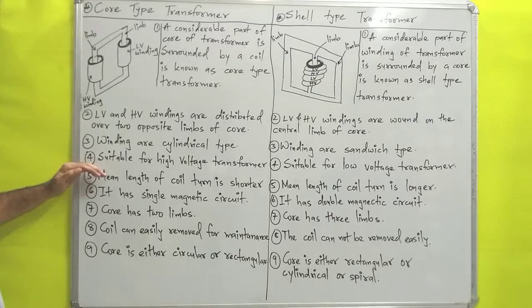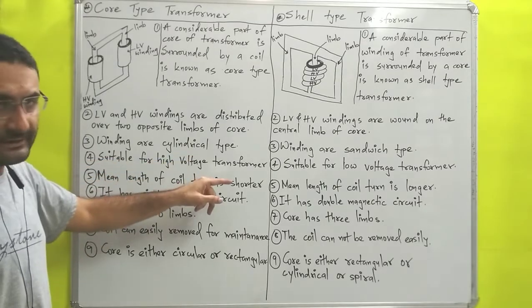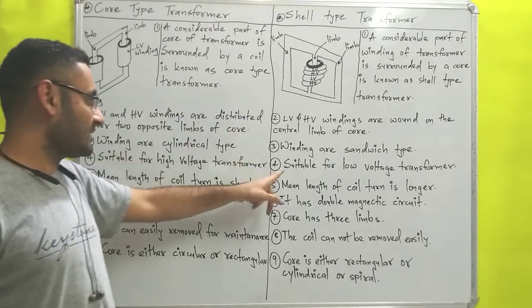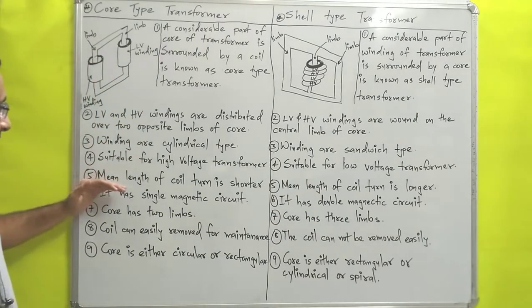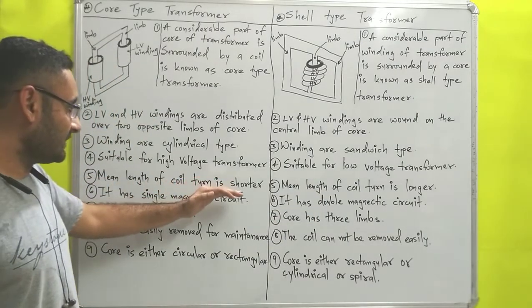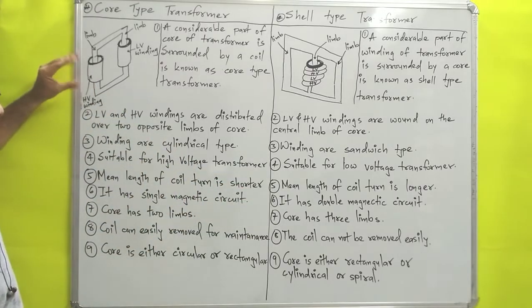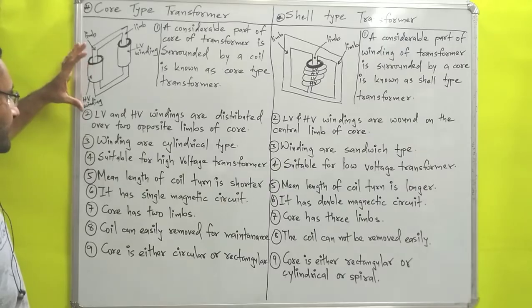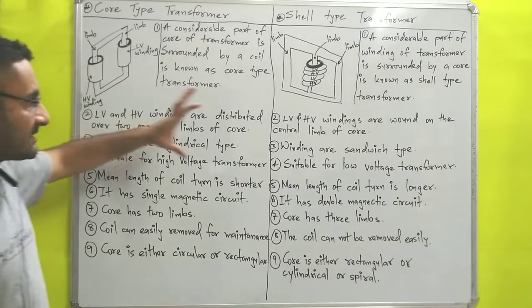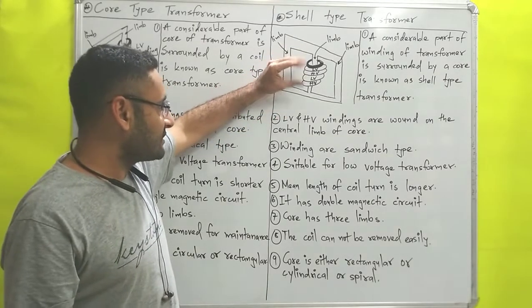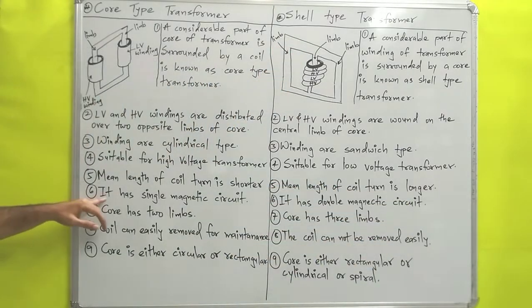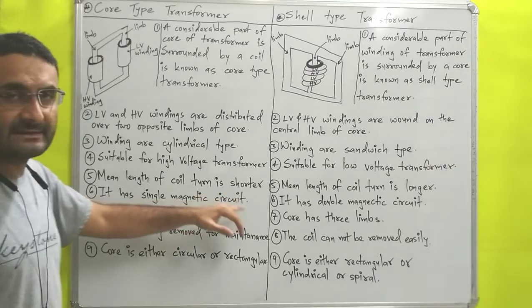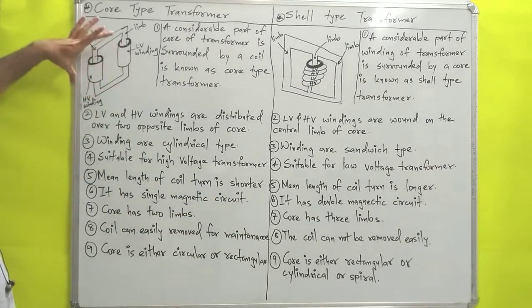The fourth difference is that the core type is suitable for high voltage transformers, while the shell type is suitable for low voltage transformers. Next, the mean length of coil turns in the core type is shorter, because the windings are tightly wound near to each other, so the length of the coil is less. In the shell type, since the windings are sandwiched, the length of the coil turns is longer.